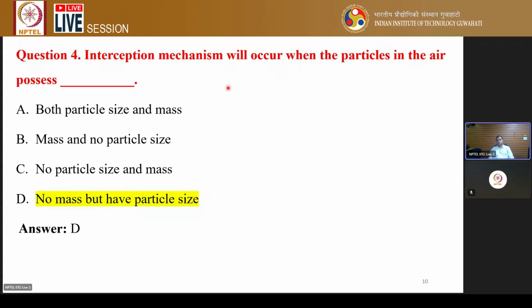Typically we use a HEPA filter. The mechanisms of a HEPA filter are inertial impaction, interception, diffusion, and electrostatic attraction. Inertial impaction is based on mass and size, but interception is purely based on size. So the correct option will be: no mass but have particle size.